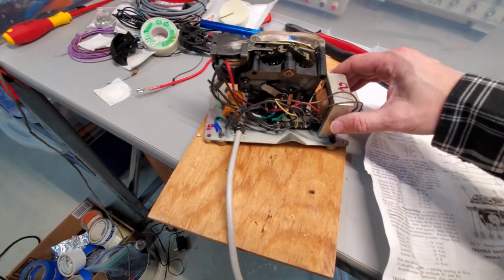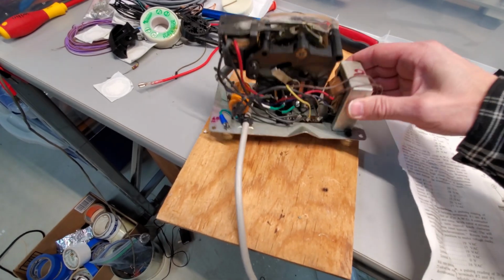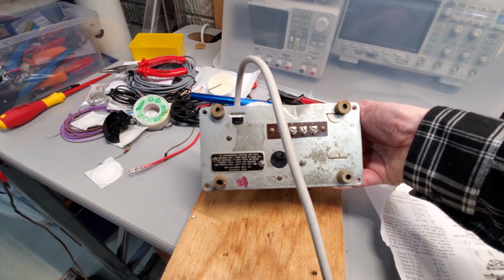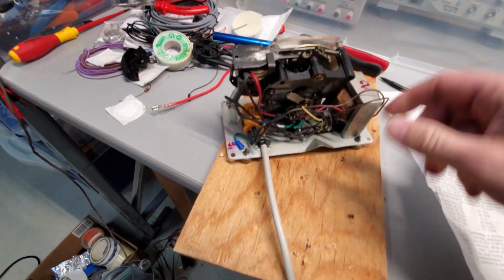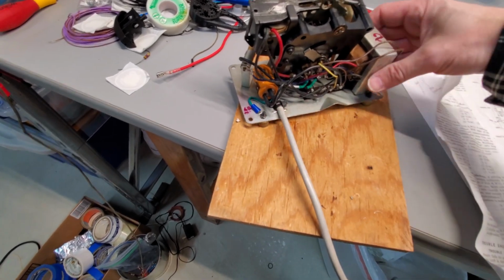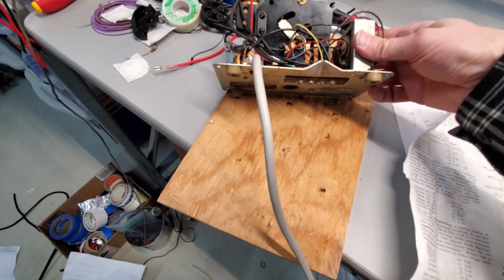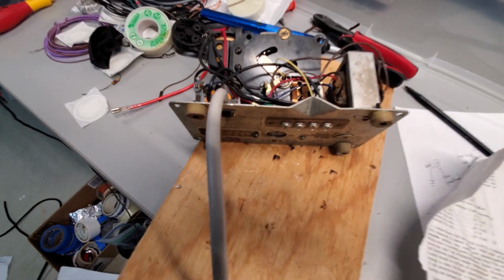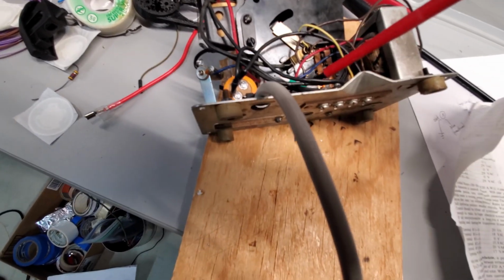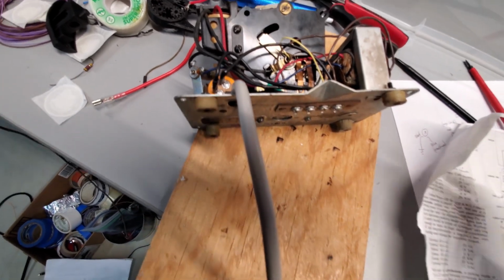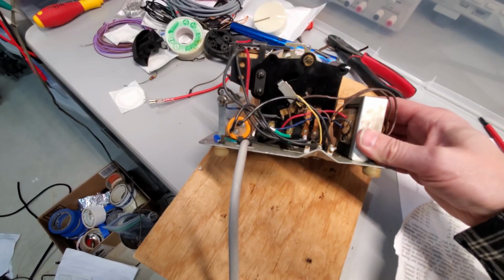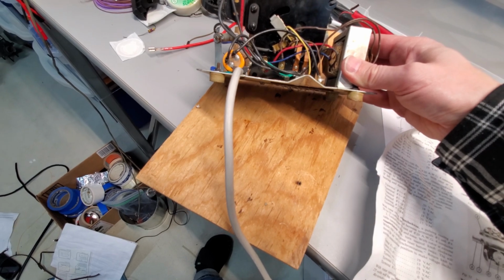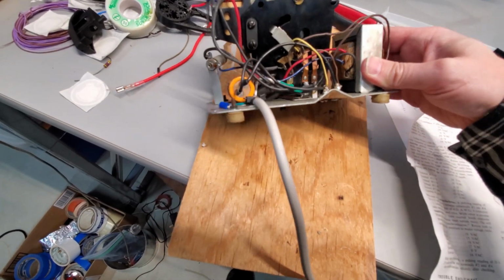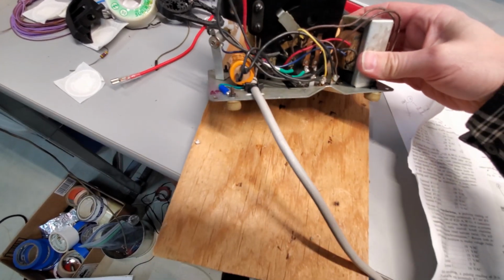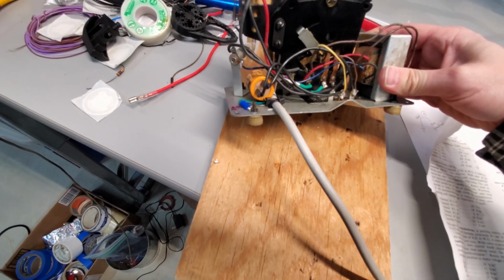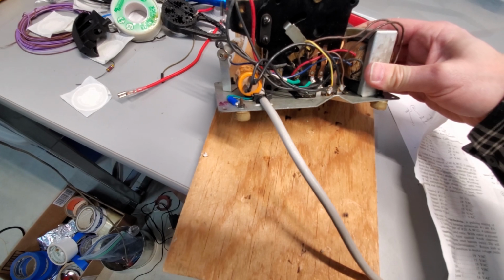So before I close this case on the control box—again, that's the model U-83—what I did is go ahead and replace the power cord, so I have a ground here, because this metal piece is exposed and you could touch it. Normally it's totally fine, but if one of the power wires breaks off and touches the metal housing, the metal housing will be under voltage, and if you're touching it, you might become the path to ground, which wouldn't be great. So according to standards, at least in Germany, I've grounded the case, so that should be a little safer.